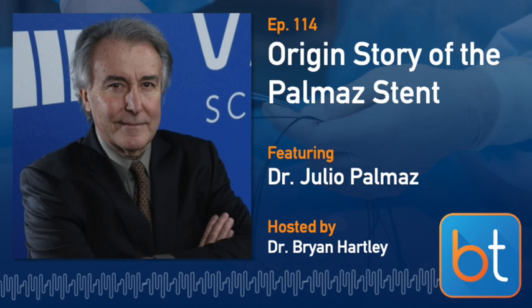You had the mind to go deep into the science. Hearing you talk, you were not afraid of going into areas that had never been explored before. It's pretty impressive how far you can go on a theory basis. You don't have to have practical steps in between to move on to the next problem. You can go quite a long time on an empirical basis. You have to convince yourself that things make sense from the science point of view. For example, things that are not going to be biocompatible or may pose a problem: the minute you start reading what is in the literature about metal implants and dissimilar metal corrosion, it's all there. You just have to apply it to your needs, and synthesize it.